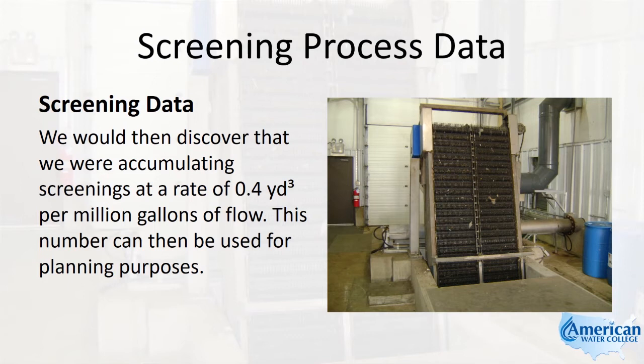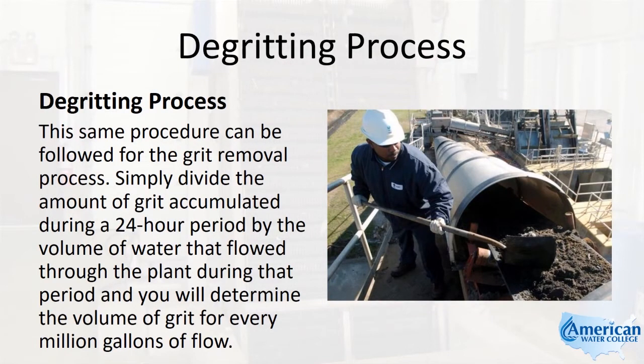This number can then be used for planning purposes. This same procedure can be followed for the grit removal process. Simply divide the amount of grit accumulated during a 24-hour period by the volume of water that flowed through the plant during that period, and you will determine the volume of grit for every million gallons of flow.